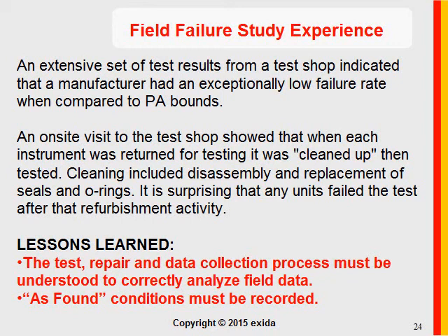So we took a visit to the test shop to learn exactly how the instruments were evaluated and classified as a failure or not. Look at this. What we discovered was that before each instrument was tested to see if it failed or not, it was cleaned up. Cleaning included, you won't believe this, disassembly and replacement of seals and O-rings. And I was thinking to myself, I'm shocked that any units failed after that refurbishment activity.